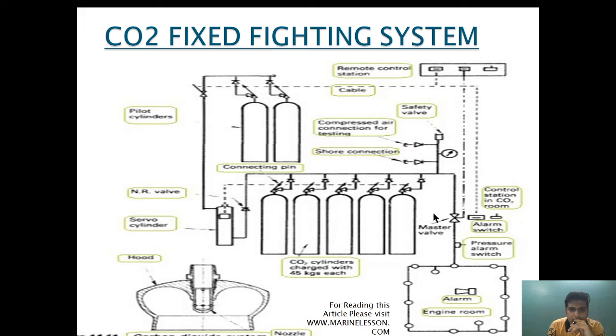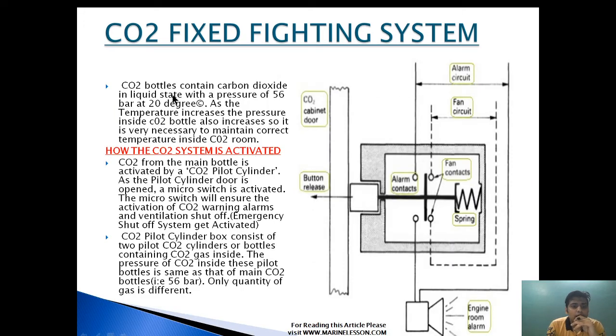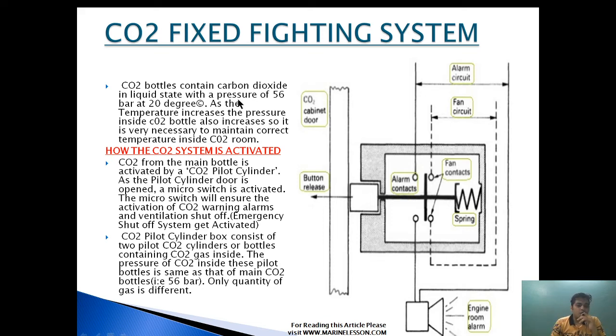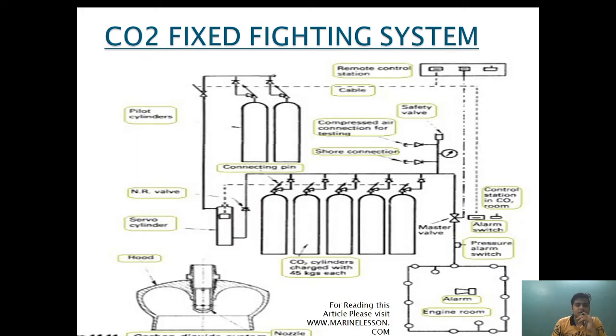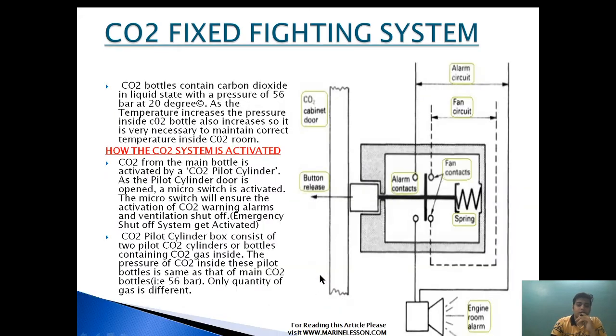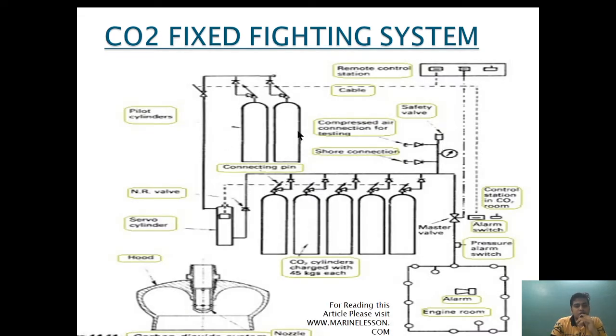CO2 bottles contain carbon dioxide in liquid state with a pressure of 56 bar at 20 degrees Celsius. As the temperature increases the pressure inside a CO2 bottle also increases, so it is very necessary to maintain the correct temperature. The CO2 room temperature should always be maintained around 20 to 35 degrees Celsius to prevent over-pressurizing the CO2 bottle. Each CO2 bottle consists of 45 kg of CO2 charged at 56 bar. The pilot cylinder pressure is also the same: 56 bar.